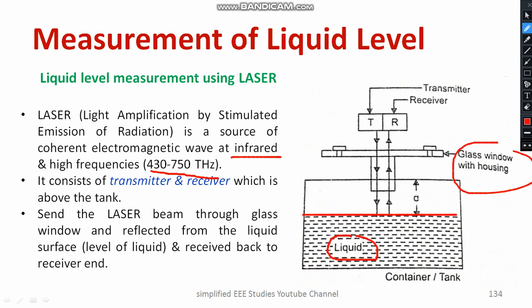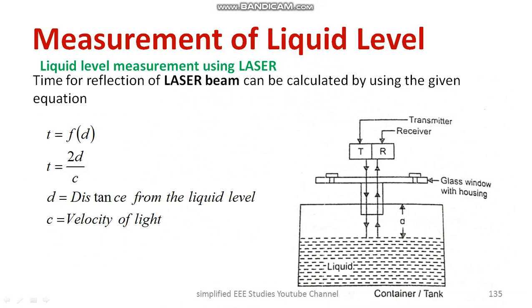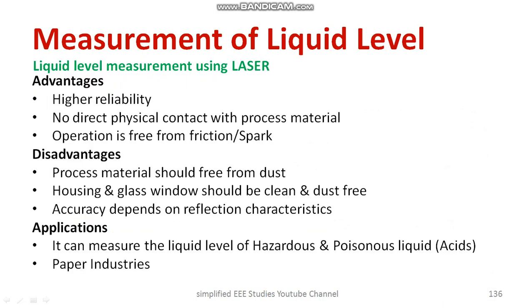There is a glass window. The laser beam is sent through the glass window, reflected from the liquid surface, and received back at the receiver end. Here we are using the principle of reflection. The time is a function of the distance d, where d is the distance between the upper layer of the tank and the standard height of the liquid. The formula is: time = 2d / c, where c is the velocity of light. So time can be computed, and with respect to the time you can determine the liquid level.